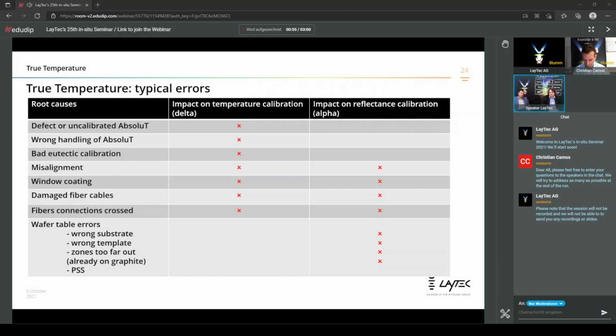This is a more software-related and not hardware-related root cause for a typical error. We sometimes see that users set up their wafer table in a wrong way and don't maintain a consistent wafer table setting. You all might know wafer table as the typical term used, or still used, in EpiNet 1. Now in EpiNet 2, there's a very nice graphical wafer table editor, the so-called runtime editor, and it very easily walks you through the process of configuring your measurement setup. And actually, the result of the runtime editor ends up in a wafer table. So the final configuration result is the equivalent wafer table setup as in EpiNet 1.